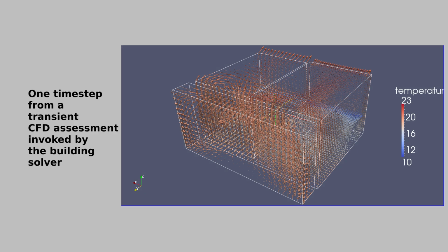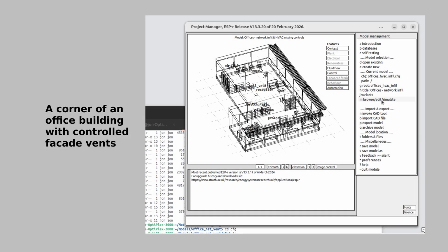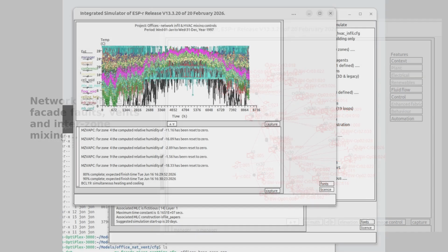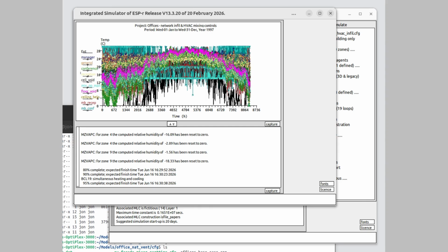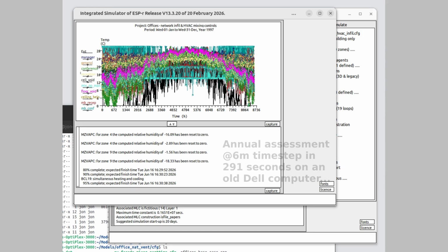there's network flow. It's an approach to describing airflow paths and effectively solving mass flows in a building, and it does so very efficiently. For context, I could solve a moderately complex flow network with, say, a 1-minute time step over lots and lots of months, and that would take roughly the same time as solving a moderately simple CFD domain over a few time steps.